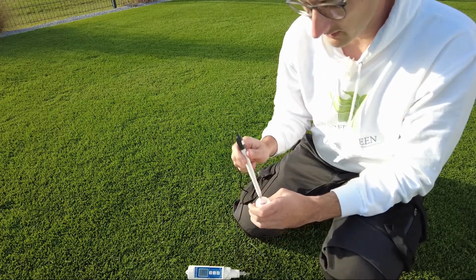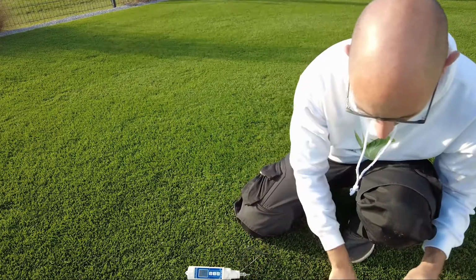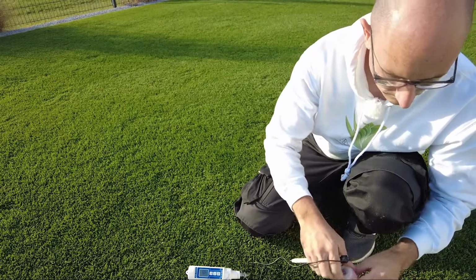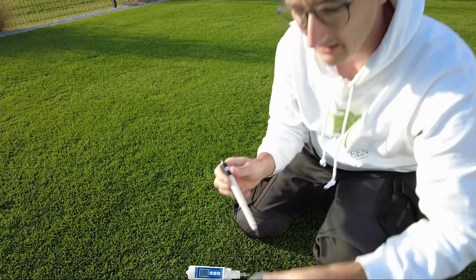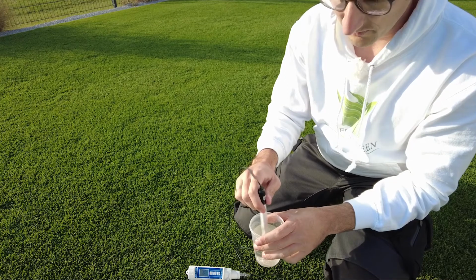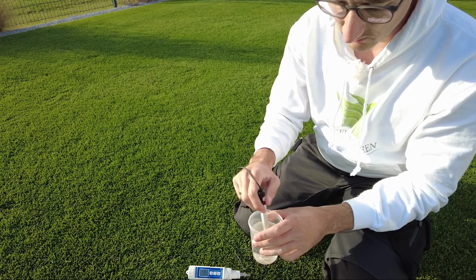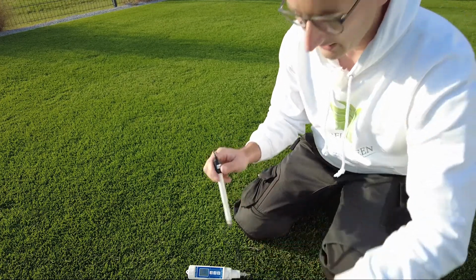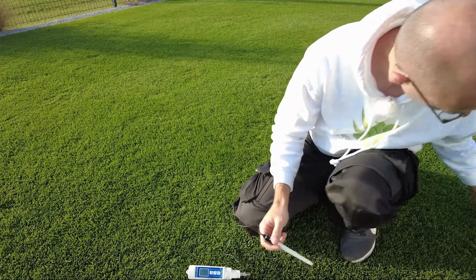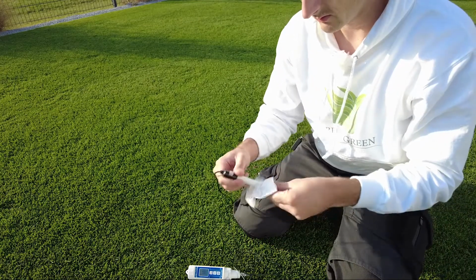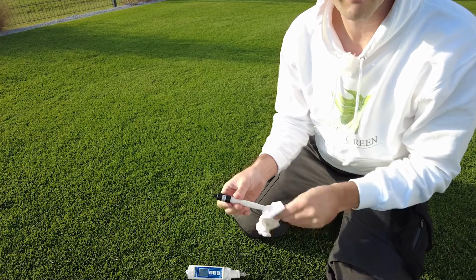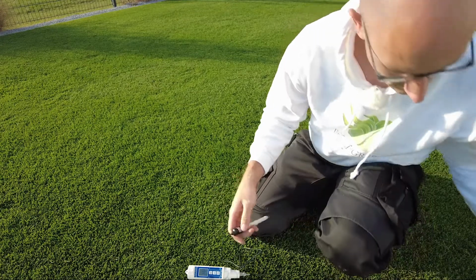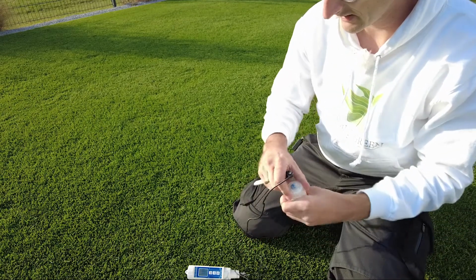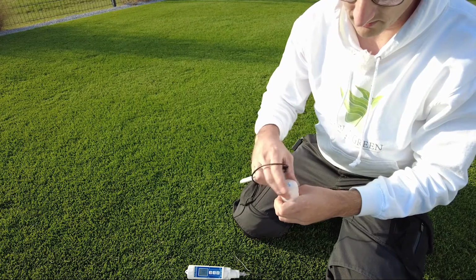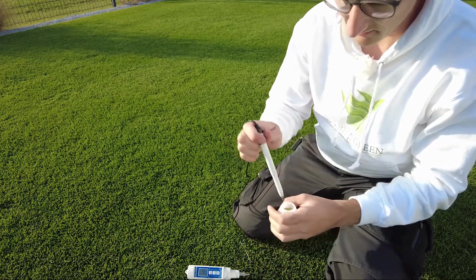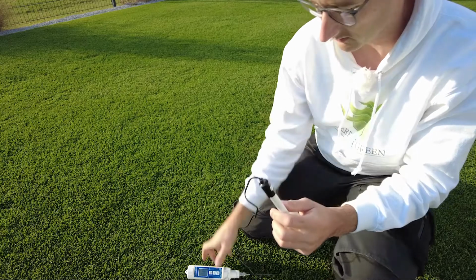We take it all now out of the solution, screw the cap carefully back on, and calibrate the same now in pH value 7. I clean it all again, dry it, and also calibrate it with pH value 7. And then we can be sure that this device functions perfectly for our ground.